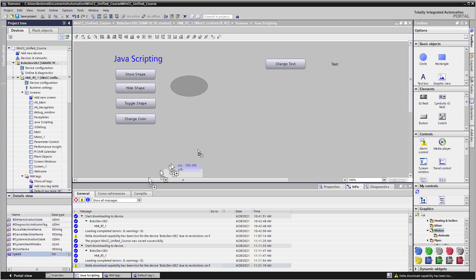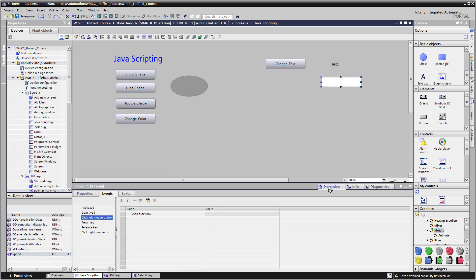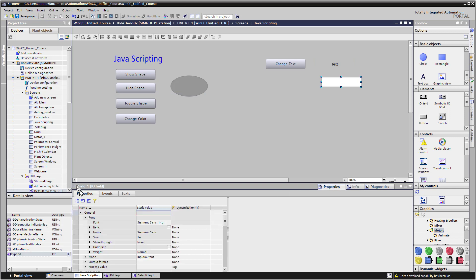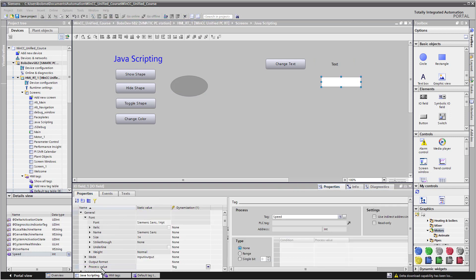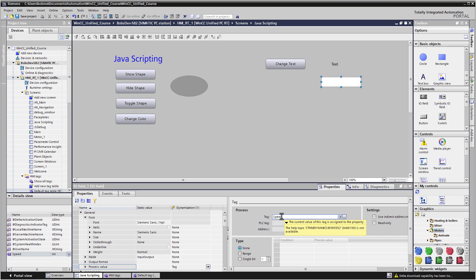notice that I still have my default tag table selected. And there's my speed tag. So I can just drag this up and drop it. And if we look at the properties, we find that that is just an IO field that was created. And if you look at your process value property, you can see that it is connected to the speed tag. So in runtime, we will be able to see the value of the speed tag as well as change it.